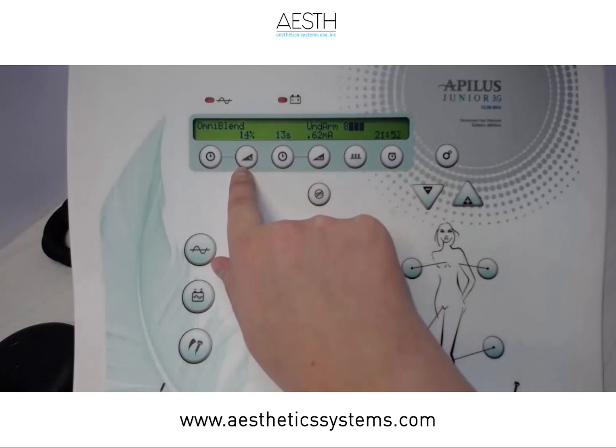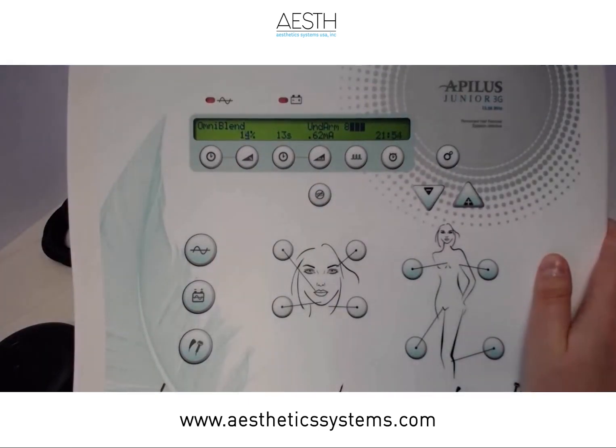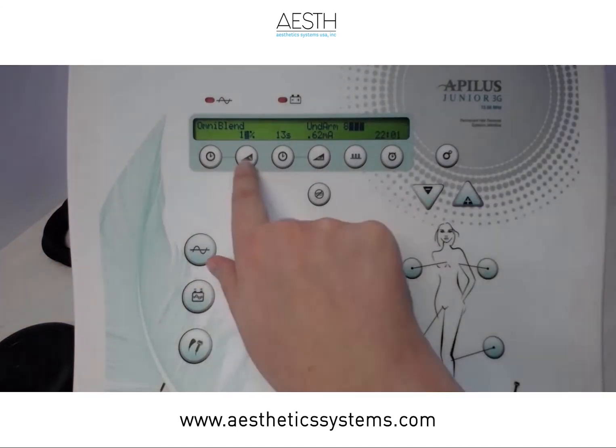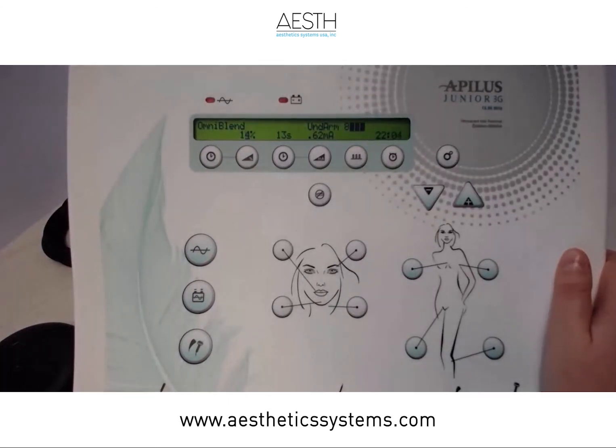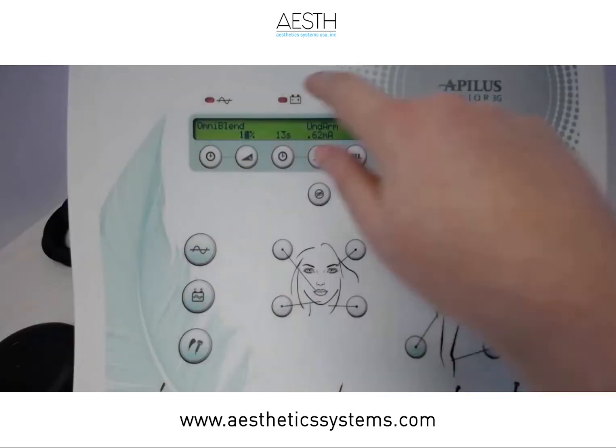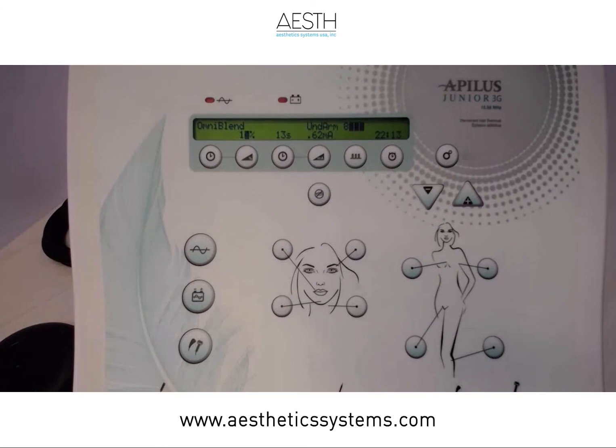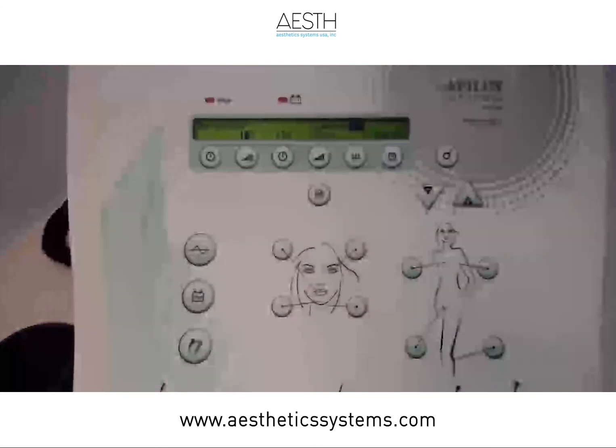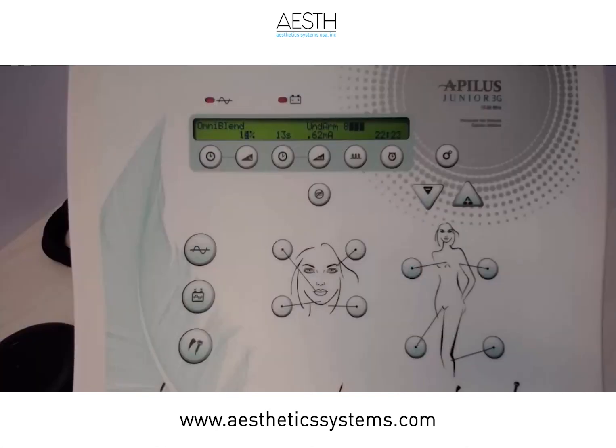What I pressed here was to display the percent under the OmniBlend. The OmniBlend has continuous high frequency, so you can change your high frequency by pressing down underneath here. There's no time for high frequency because it's continuous, so it doesn't matter - this key won't show anything. But here you have 14%, and you can go up and down from there. Just be careful, because too much high frequency will start to coagulate, and coagulation dries out the tissues, and if you don't have moisture, you can't create the lye.